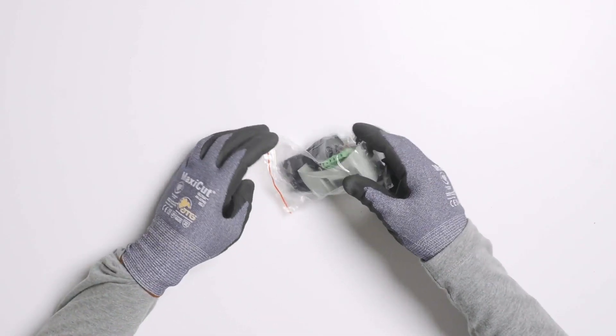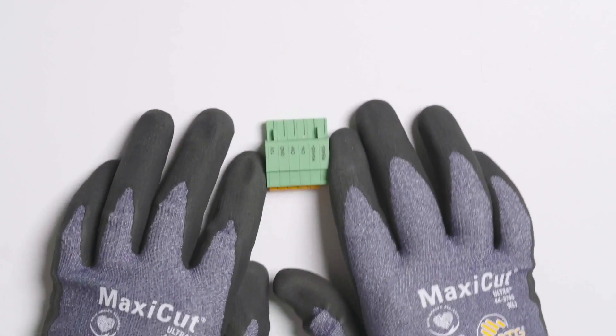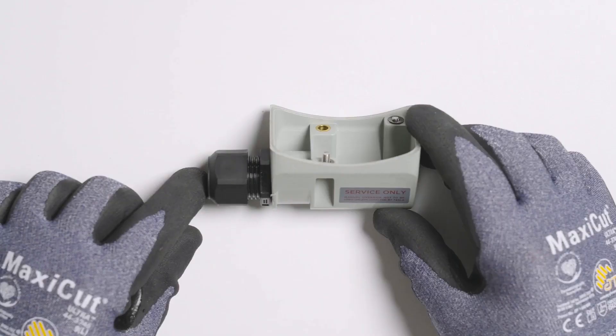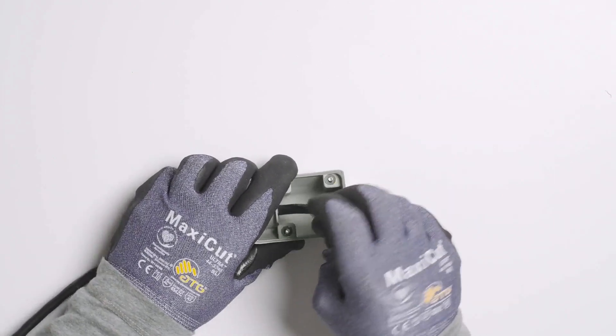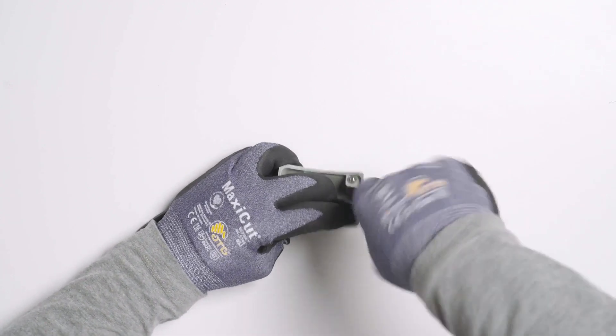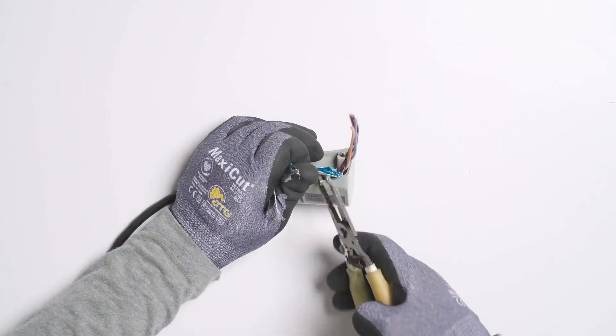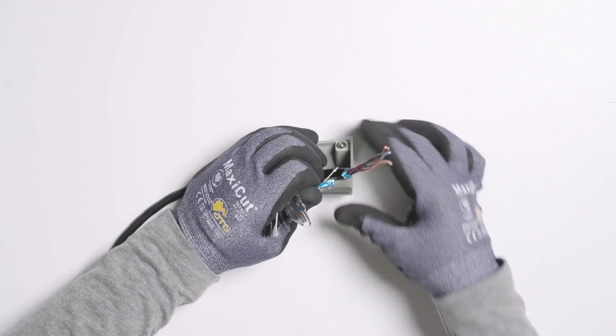A four-wire communication cable connects Backup Switch to the site controller. From the Backup Switch accessory bag, retrieve the conduit hub, cable gland connector, and the green connector. Thread the connector into the conduit hub. Run the four-conductor communication cable through the connector and the conduit hub. Remove the outer jacket to expose the four conductors within the cable. Cut the drain wire back flush with the end of the outer jacket.